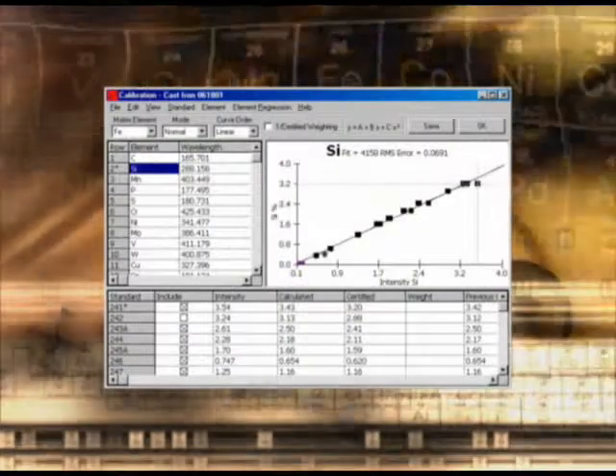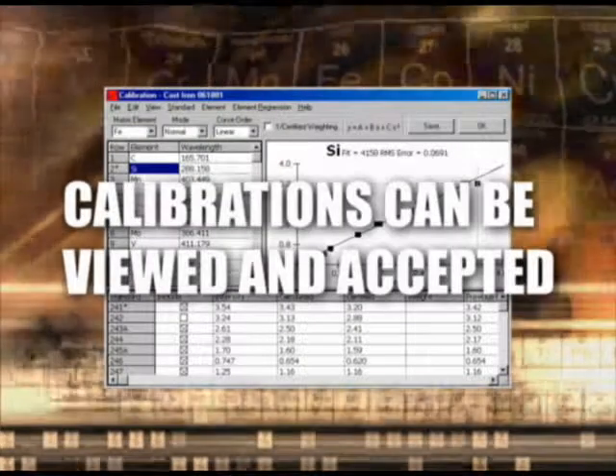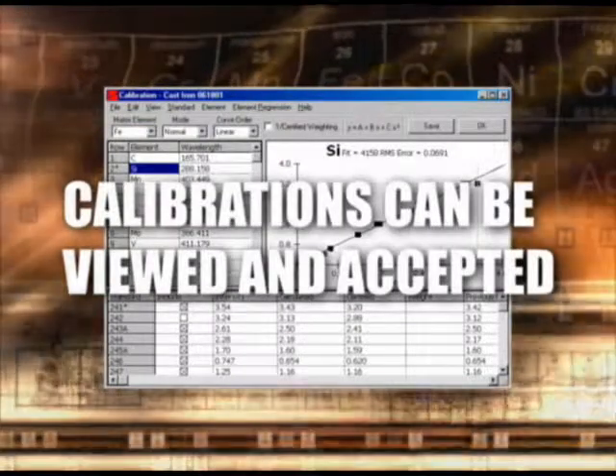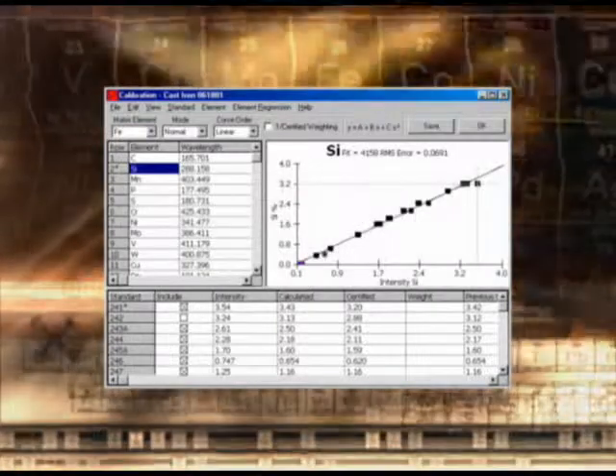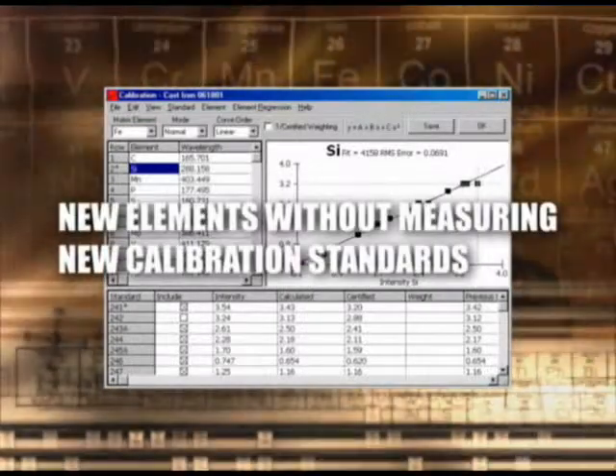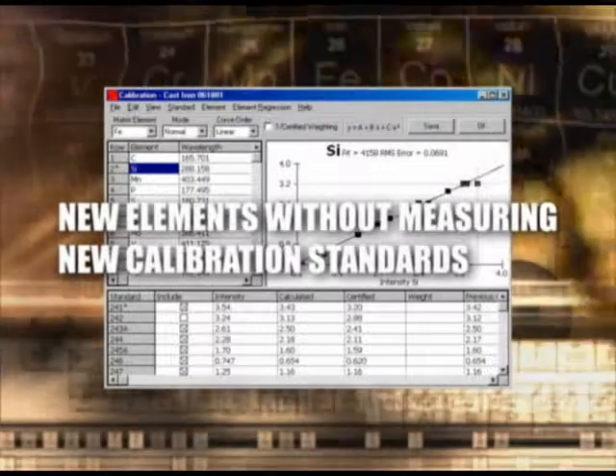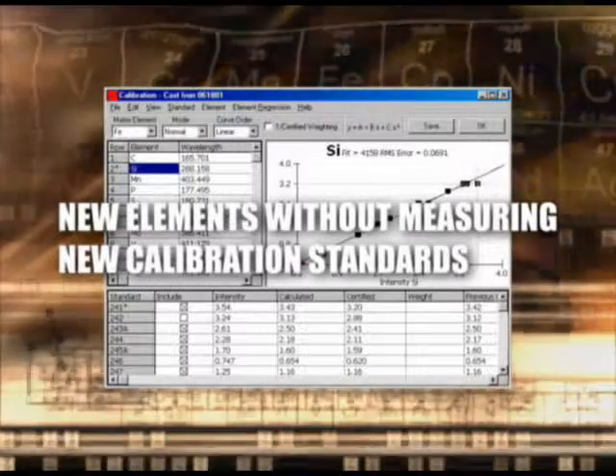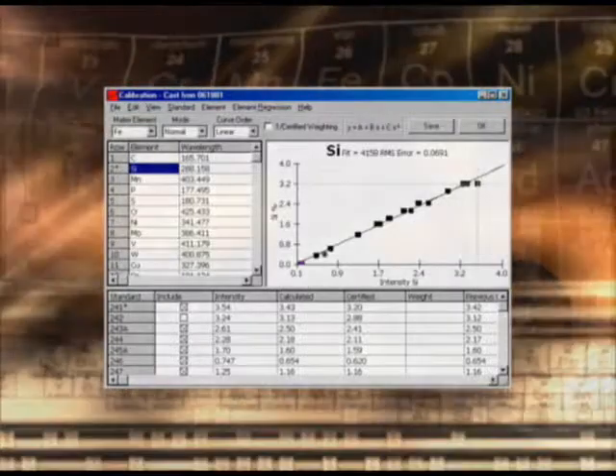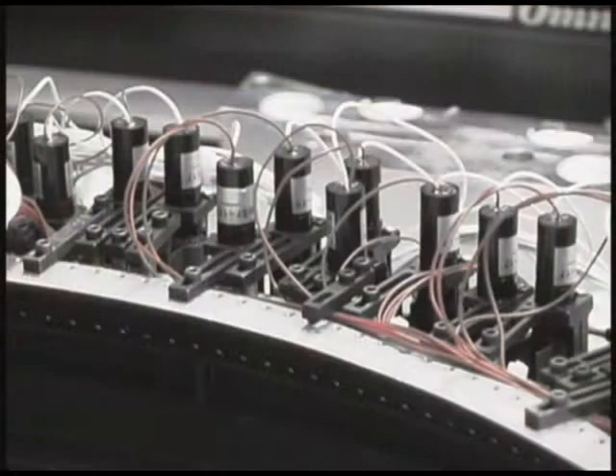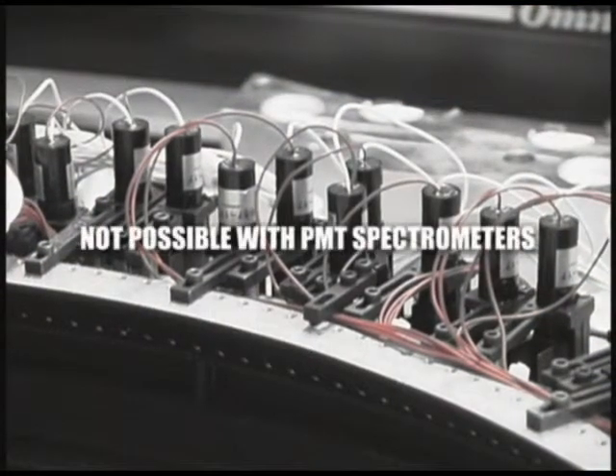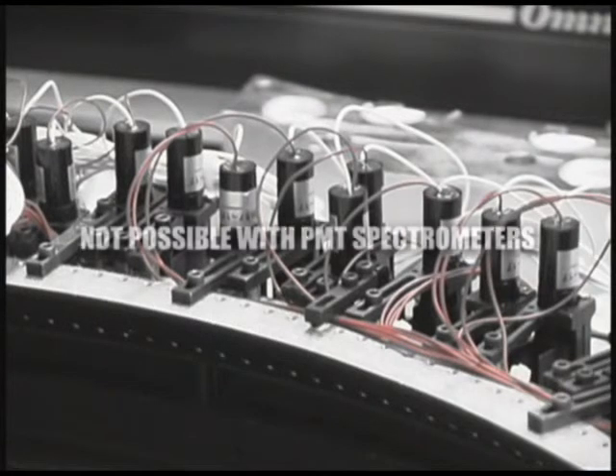Because the CCD spectral data for each standard analysis is saved, a new calibration for another element or element line can be added to the system without having to rerun any standards. This flexibility is not possible with PMT-based systems, which only measure specified wavelengths.